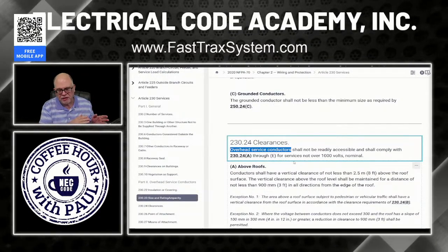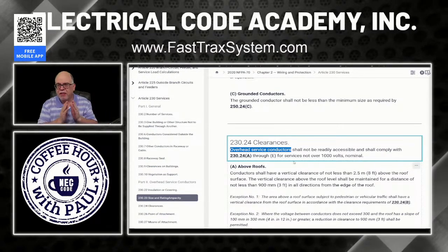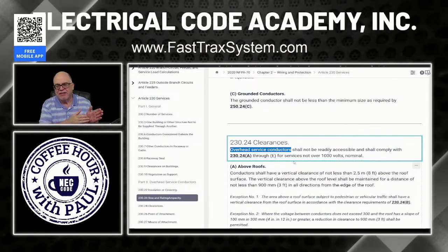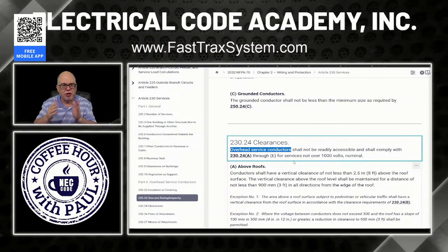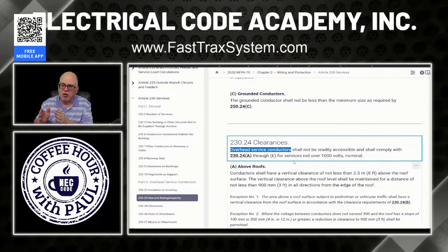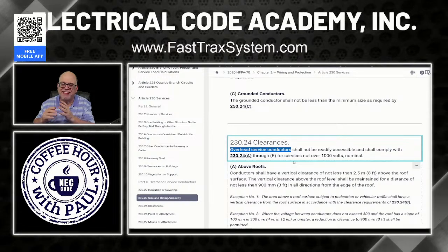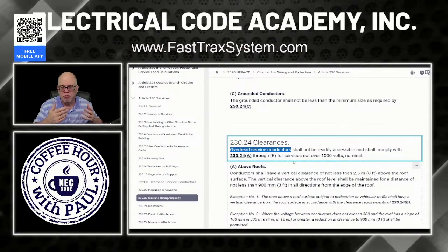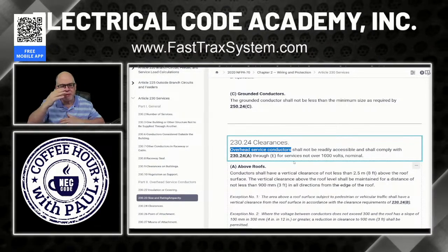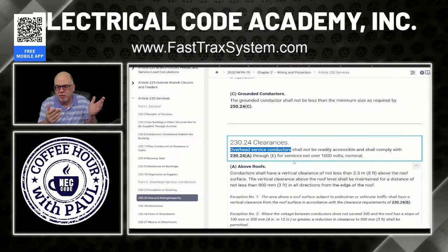That's an important distinction, folks, because if you go look at Article 100 and look at the definition of service drops, this is typically controlled by the utility, and they dictate the height and clearances. Now, most of the time, they're going to mirror the NEC, but they dictate that. So when you install your point of attachment and your securement to the building, while it's not necessarily the NEC's responsibility for these clearances on service drops, you have to make sure, because obviously you've got to meet the utility's requirements too, or they're not going to bring the service to your building.